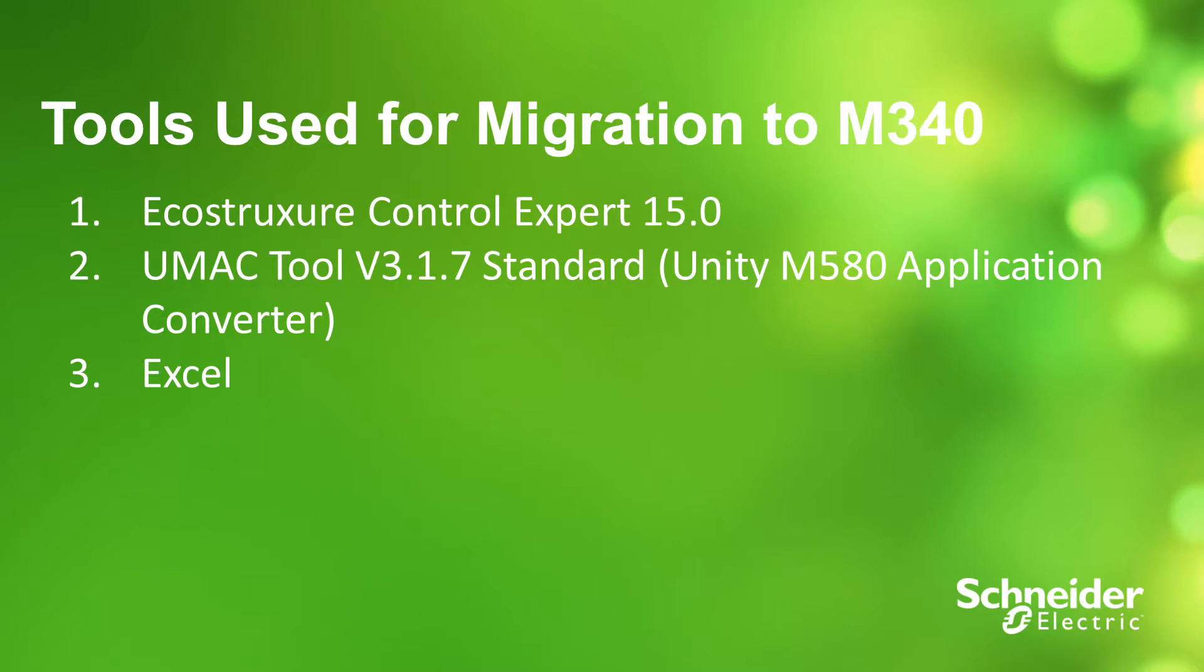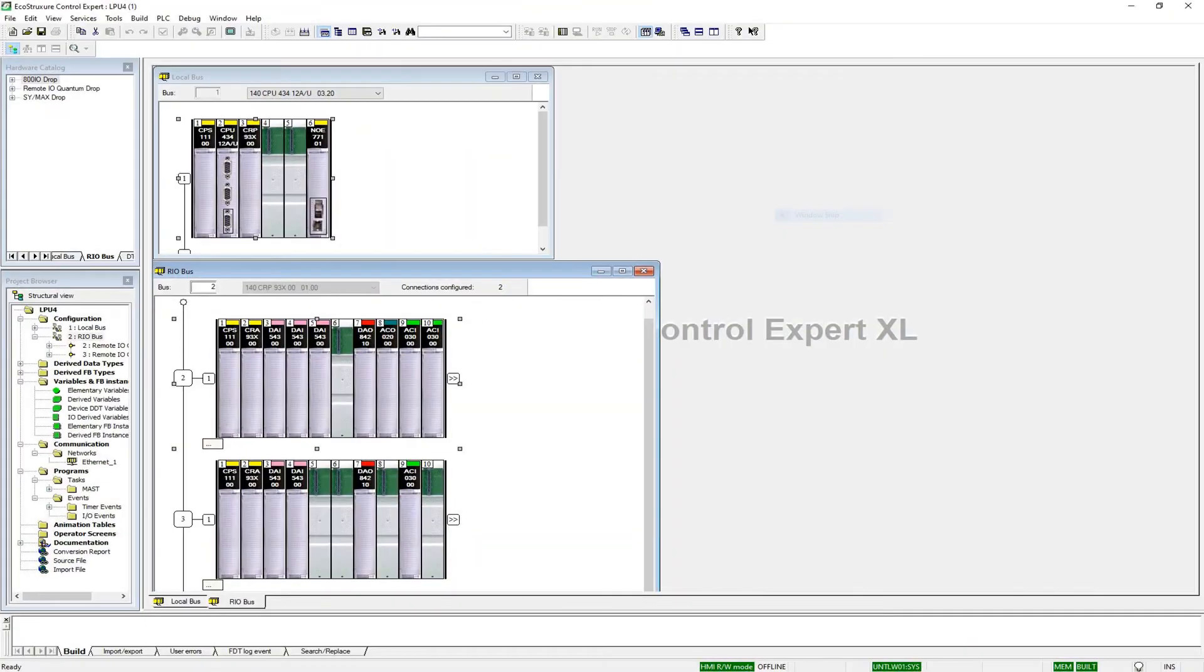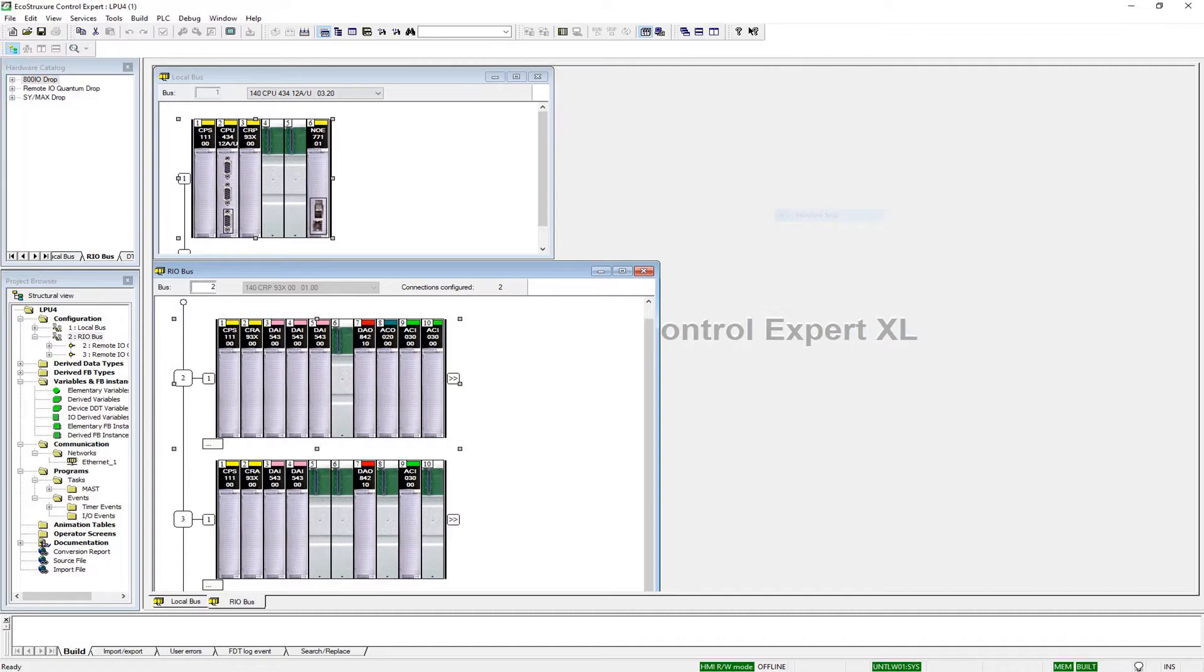The tools utilized to perform the conversion are EcoStruxure Control Expert version 15, Unity M580 Application Converter UMAC Tool version 3.1.7 standard, Excel to record state RAM addresses, Ethernet settings, and other parameters that may not carry over to the new program during the conversion process. The project to be converted is for a Quantum 140 CPU 434-12U processor with two S908 remote racks. The program will be converted to an M340 with local I/O.